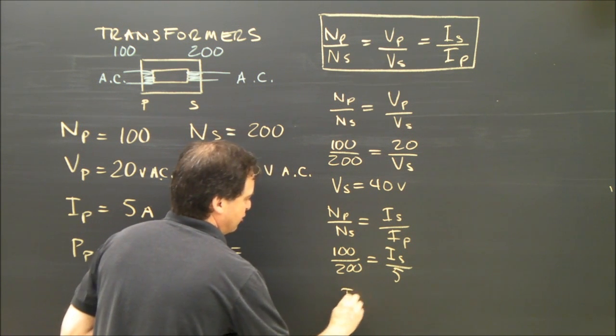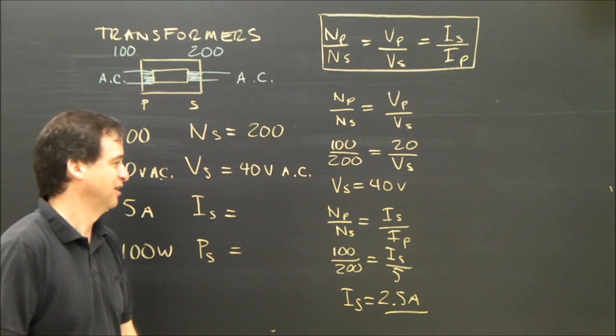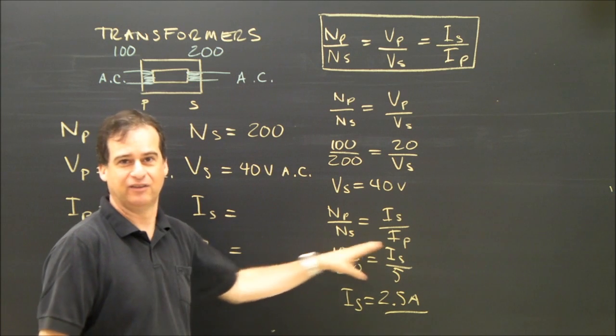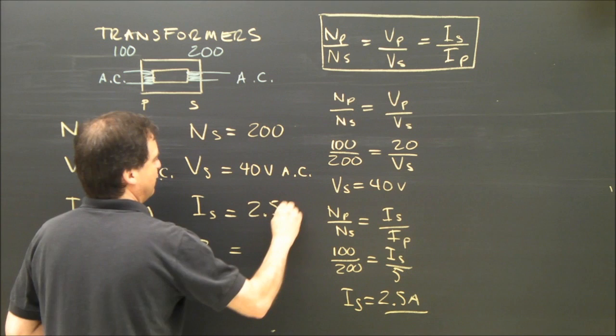So we've got 100 over 200 equals current in the secondary over 5. Rearrange that. Current in the secondary should be 2.5 amperes. So you can work that out. It should work out. Yeah, it should. Half of that, half of that, they're equal. Okay? Now, current of the secondary is 2.5 amperes.